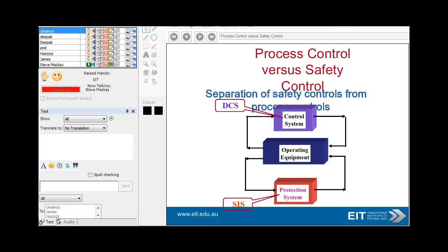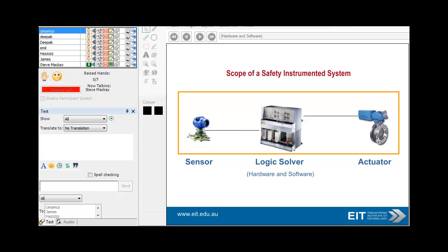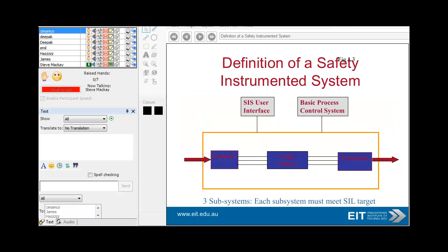It is very important to separate the safety controls from the process controls. You have your operating equipment and your protection system — these are two different issues and need to be looked at separately. The scope of a safety instrument system covers the sensor, the logic solver, and the actuator. Each subsystem must meet the SIL target.